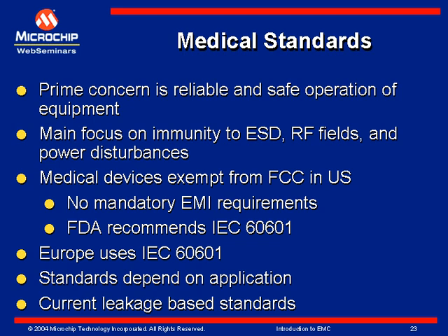Like you need much more reliability in a pacemaker than in a heart monitor. If anything is life critical, and failure of that equipment can cause a life-threatening injury, then it needs to meet much more stringent requirements than if it's used just for monitoring, where you can rerun a test.